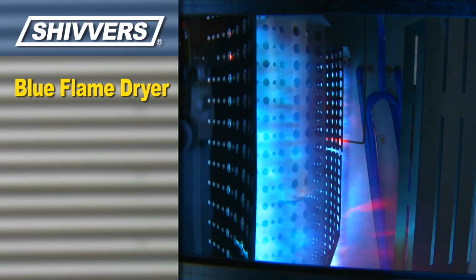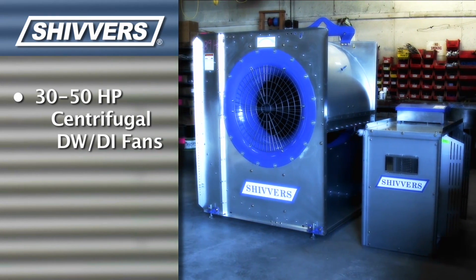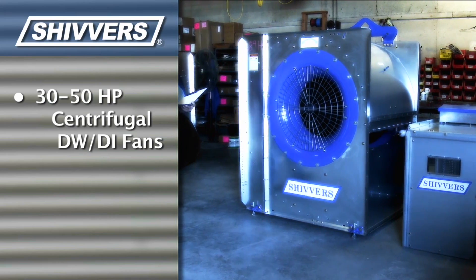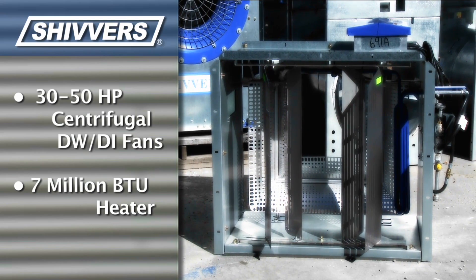The air under the floor is heated with one or more Shivvers Blue Flame dryers, which feature a 28-inch axial fan and a 3.65 million BTU heater. Also available are 30 to 50 horsepower centrifugal double-wheel double-inlet fans for increased airflow, and heaters producing up to 7 million BTUs for use on large installations.